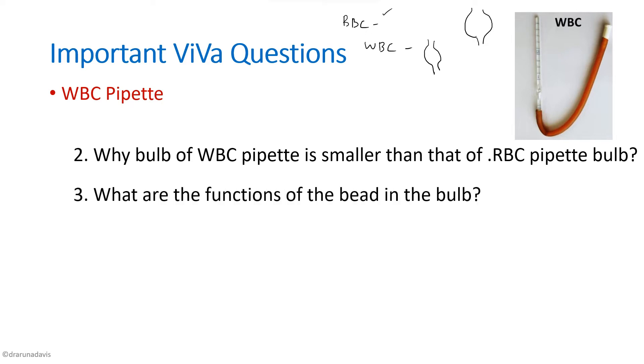What are the functions of the bead in the bulb? The bead mainly has three functions. One is for identification. Next, it is for proper mixing of the diluting fluid and the blood. Third is to know whether the pipette is absolutely dry or not. If the pipette is not dry, the bead will stick to its surface, whereas if it is completely dry, it will move around freely.